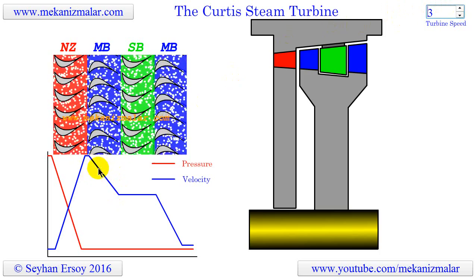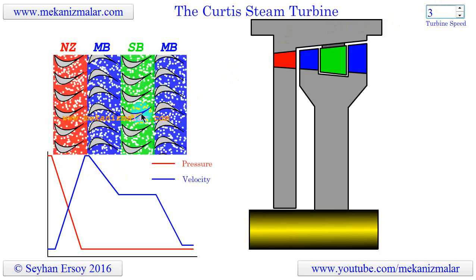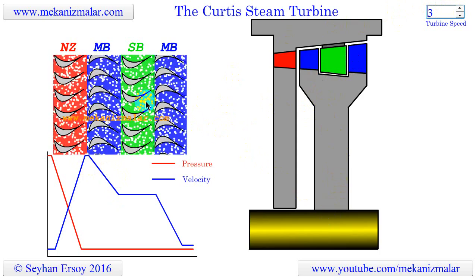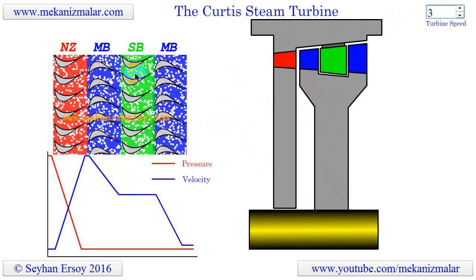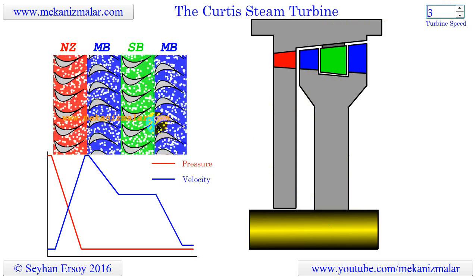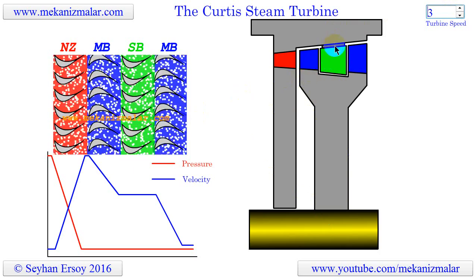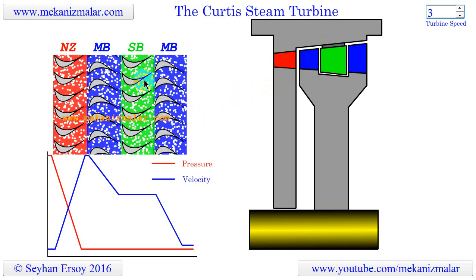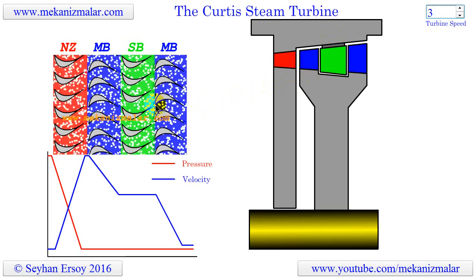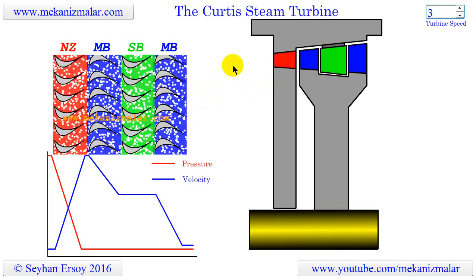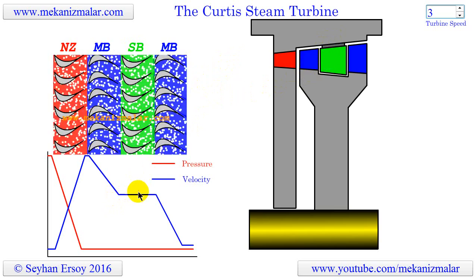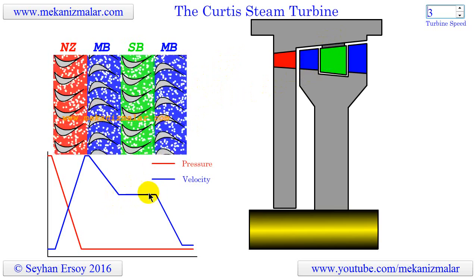The blades in the moving blade stage are attached to the rotor of the turbine. The green flow in the next stage corresponds to a stage where the steam velocity changes direction. Here, the blades are stationary and attached to the turbine body, indicated by SB in the animation. The purpose of this stage is to direct the steam to the next moving blades at the correct angle. If we ignore friction, the speed of the steam in this stage does not change, as seen in the plot.